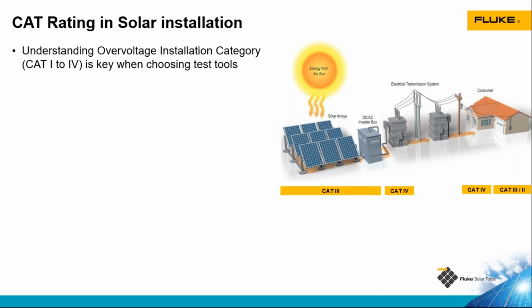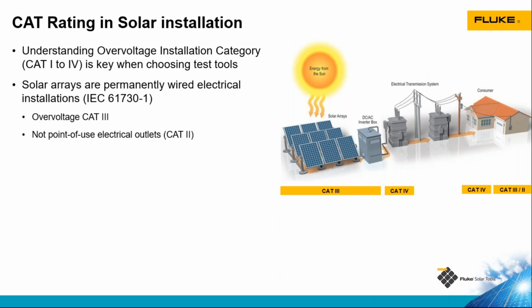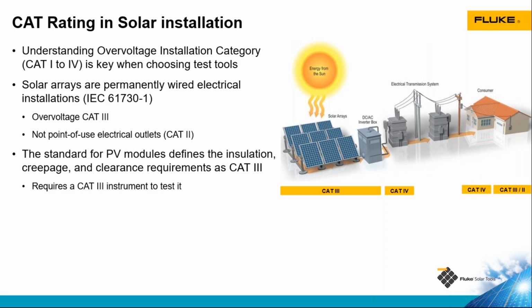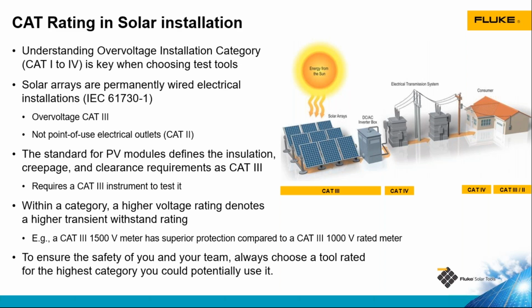CAT ratings go from 1 through 4. The higher the number goes, the higher the potential for transient voltage spikes and the greater the intensity of the transient voltage spike, and the closer we are to the source of that transient voltage spike. There's an IEC standard that categorizes DC solar arrays as a category 3 environment. That means we need to buy tools that have a category 3 rating. We also do testing in category 4 environments in solar.